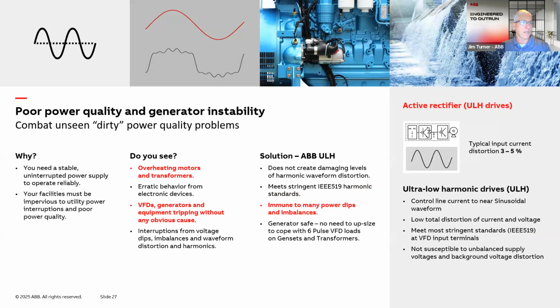This issue of poor power quality is actually only noticed once the symptoms are exposed. Things like unbalanced input voltage, voltage sags, voltage dips, brownouts, etc., along with current harmonic distortion. These are the unseen and almost undetectable issues that can cause unplanned downtime. Some common symptoms are motor overheating, unexplained instrumentation malfunctions, and emergency generators and other motor controls that may trip offline. A site level power analysis may be needed to pinpoint or correct these power quality issues.